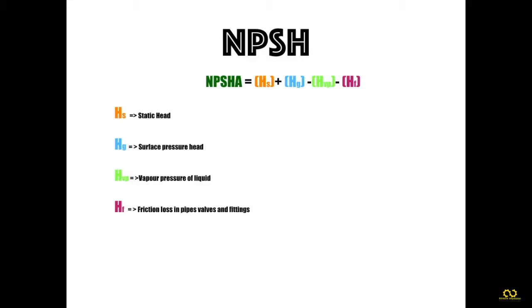To calculate NPSHA, we use the formula: NPSHA equals the summation of static head Hs and surface pressure head Hg, minus the vapor pressure of the liquid Hvp and friction loss in pipes, valves and fittings Hf. This applies to the suction line of the centrifugal pump.